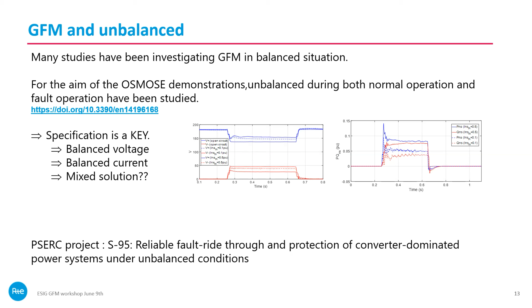Do we want balanced voltage? Do we want balanced current? Do we want a mixed solution? Do we want the same at any time of the day? Does it change depending on what your neighbors are doing, whether you have a synchronous machine close to you or not, whether you're in a remote area or not? It's tricky to specify and then to apply. On this subject, there is also, as you are probably aware, a PSERC project in which we are participating, about the operation of inverters in grid forming in unbalanced conditions and its impact on protection.